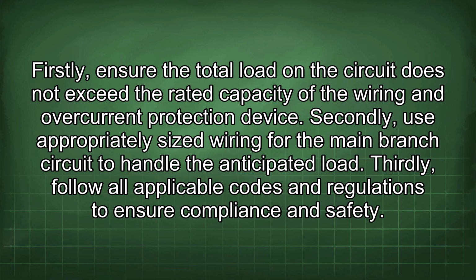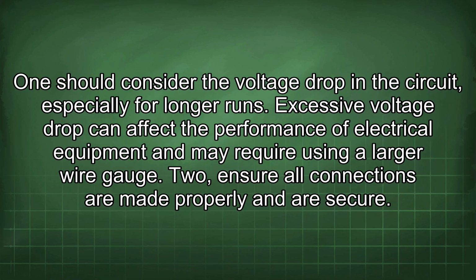Firstly, ensure the total load on the circuit does not exceed the rated capacity of the wiring and overcurrent protection device. Secondly, use appropriately sized wiring for the main branch circuit to handle the anticipated load. Thirdly, follow all applicable codes and regulations to ensure compliance and safety. One should consider the voltage drop in the circuit, especially for longer runs. Excessive voltage drop can affect the performance of electrical equipment and may require using a larger wire gauge.